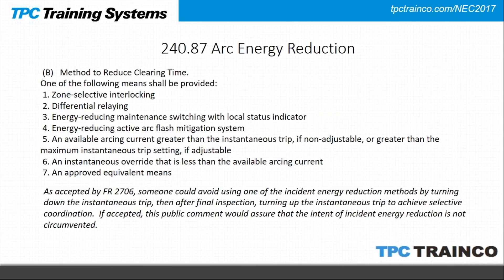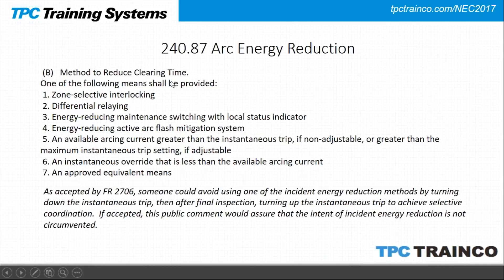Section 240.87 on arc energy reduction has been updated with two additional methods — numbers 6 and 7 — added to the existing five from 2014. Number 6 is an instantaneous override that is less than the available arcing current. This addresses a concern that someone could avoid using one of these methods by turning down the instantaneous trip and then turning it back up after final inspection to achieve selective coordination. An approved equivalent means is also permitted.